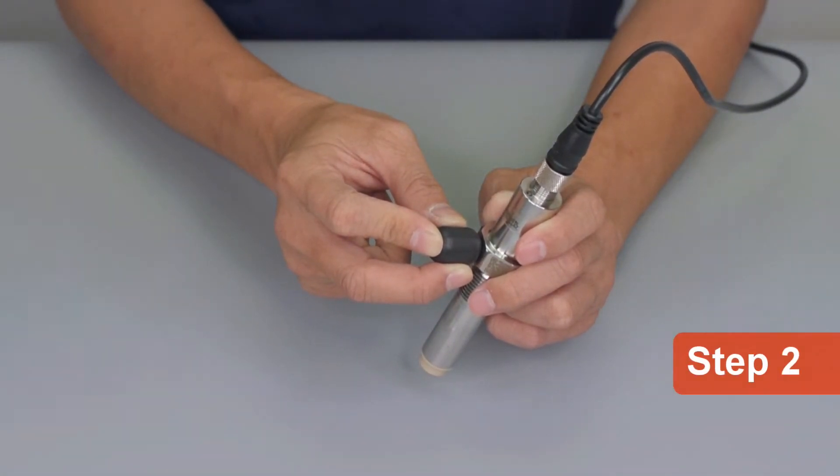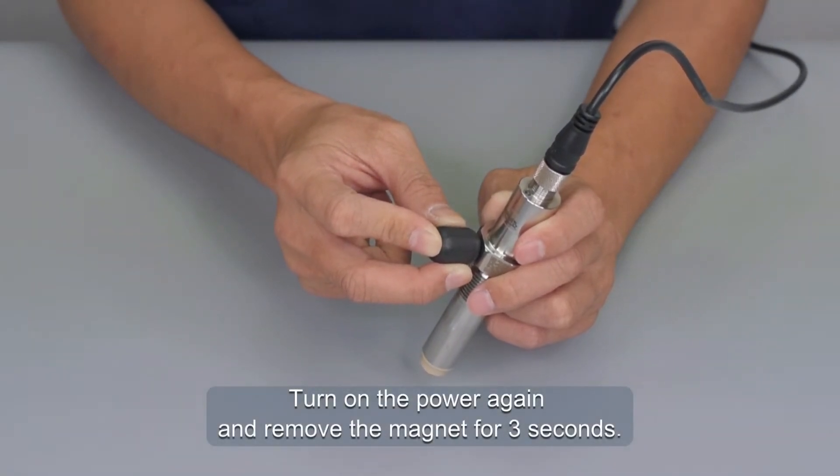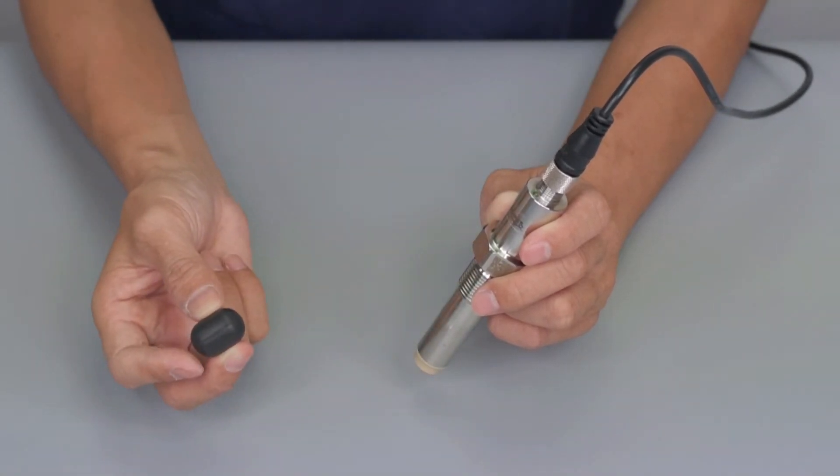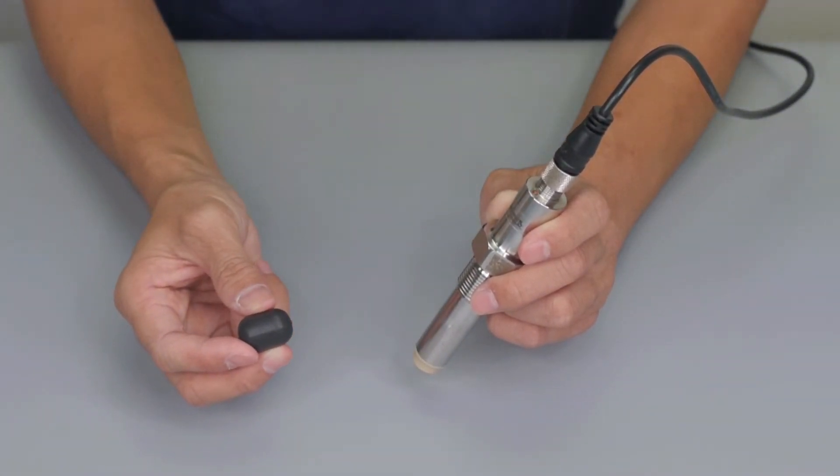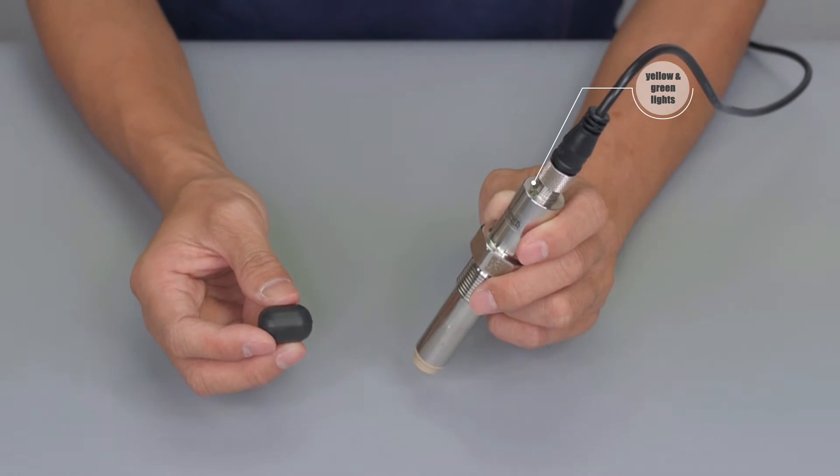Step 2. Turn on the power again and remove the magnet for 3 seconds. The yellow and green lights will flash in an interval of 2 seconds, and the sensor will be ready to be magnetically calibrated.